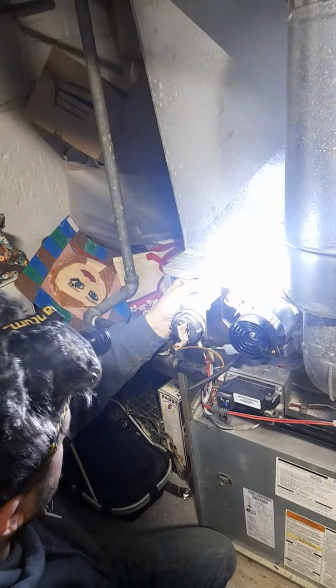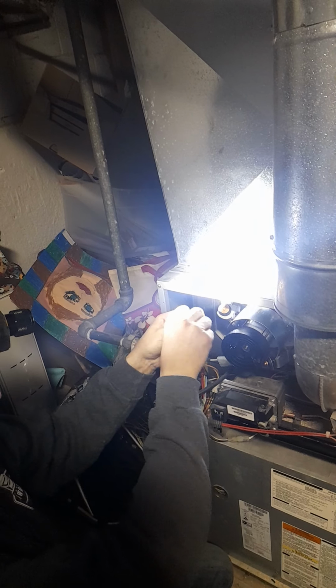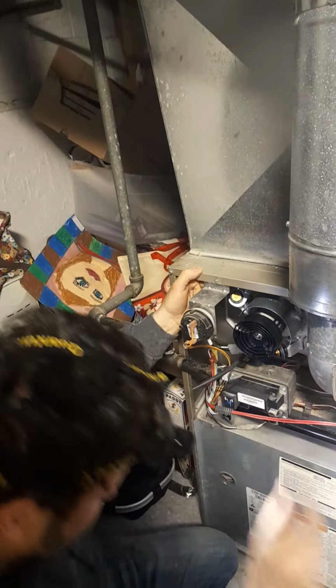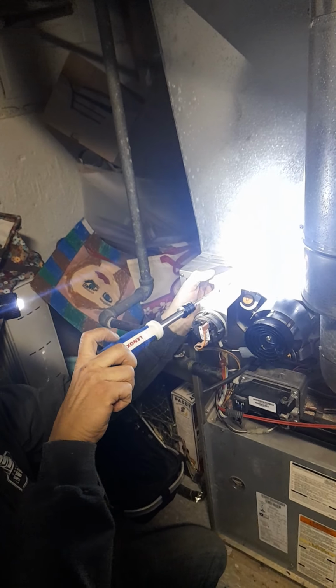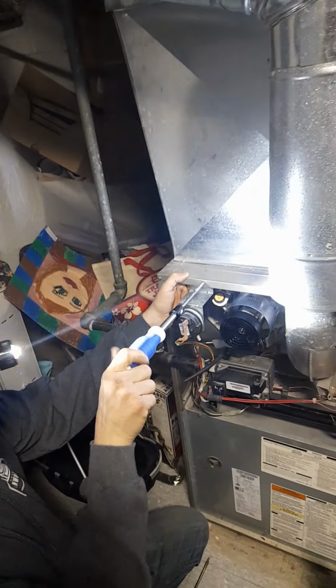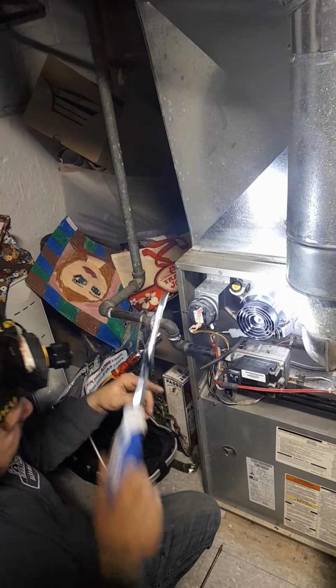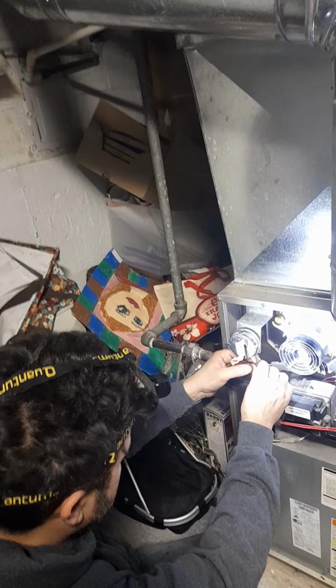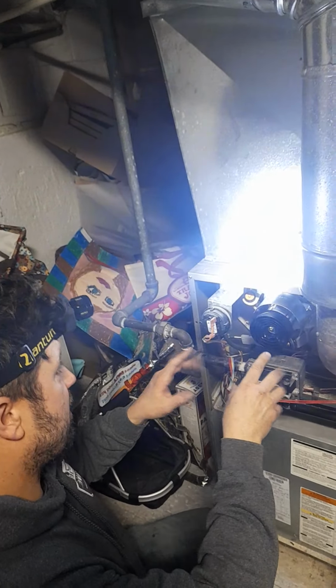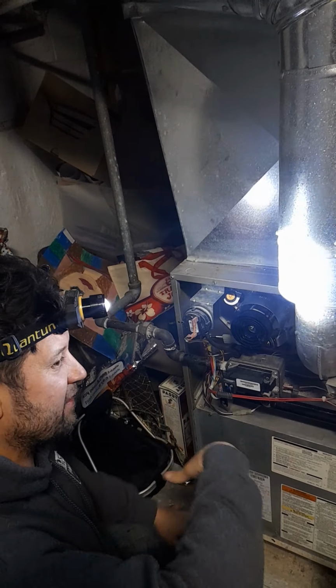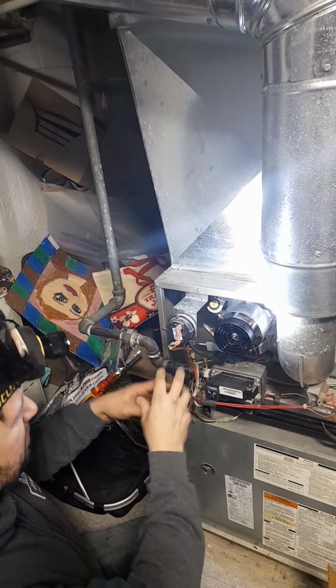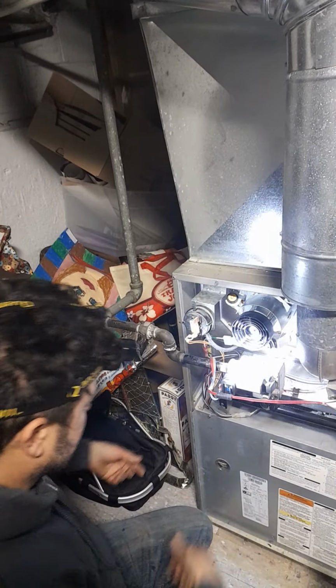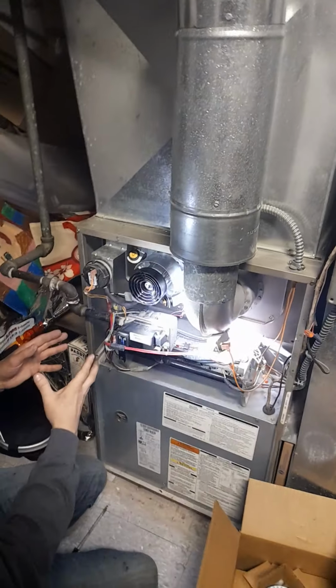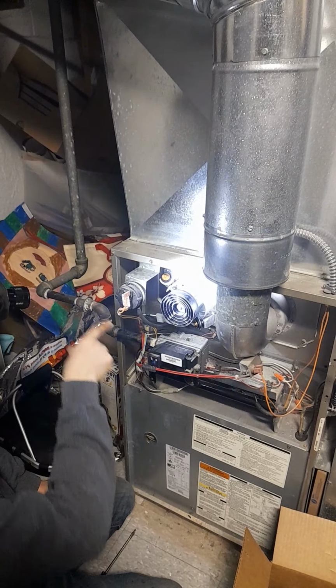And then what happens? And basically, if you get condensate, so here's the thing with some furnaces. I don't know if this is one of them, but it might be actually this one from behind. Once you get a call for heat from the thermostat, it goes through a sequence of events to make sure that the furnace is safe. The first thing it does is spin up this inducer. This switch verifies that this is actually producing enough vacuum pressure on this manifold. This switch verifies the integrity of the heat exchanger. Like if there's holes in the heat exchanger, which would allow carbon monoxide into your ambient internal air, then the switch wouldn't close because you wouldn't be able to suck enough. And I guess you've got these tubes for these burners. They're just tubes, they're called heat exchangers. You got hot gas flowing that's burning, being sucked up by this.